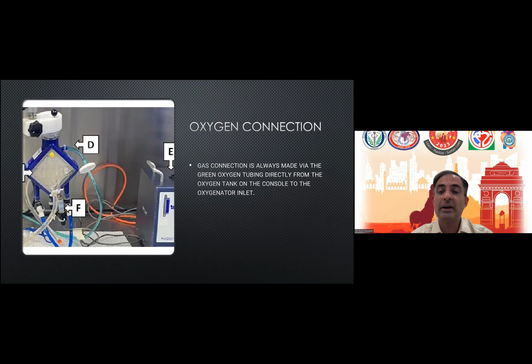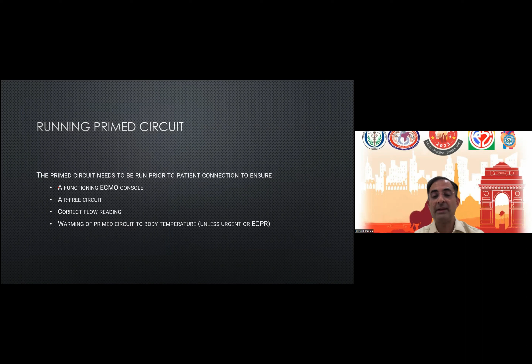Running the primed ECMO is important before we connect the patient onto ECMO, as the cannulation is being done. So the running of the primed ECMO is done on the machine or on the console to ensure optimal functioning of the ECMO, an air-free circuit, appropriate flow readings, and warming of the prime circuit to the body temperature. So this is actually a trial mechanism by which we ensure that the ECMO is optimally functioning.